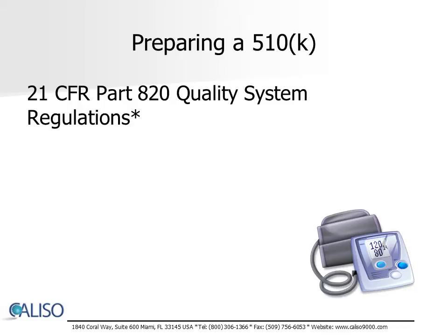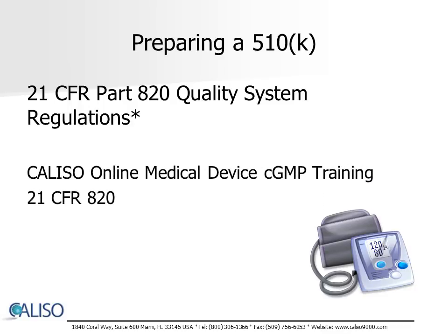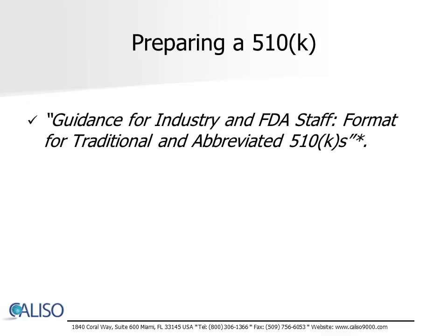The submitter may market the device immediately after 510(k) clearance is granted. However, the manufacturer should be prepared for an FDA quality system inspection at any time after the 510(k) clearance is received. CALISO does offer an online course that details the requirements of this regulation.